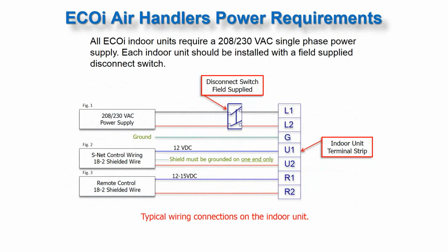Okay, ECOi air handlers power requirements. What this is showing here is how we power and wire our indoor units. Our indoor units are powered with 208/230 volt single phase power. We recommend a third-party disconnect switch before we wire our power to the indoor unit. All of our power goes to L1 and L2. Okay, and we also have a ground for this. And then U1, U2 is our communication. That's our SNet control wiring. We recommend 18 gauge 2 conductor shielded wire.